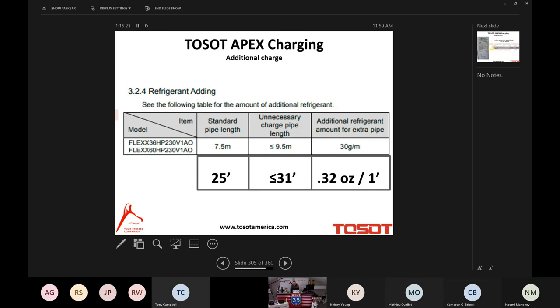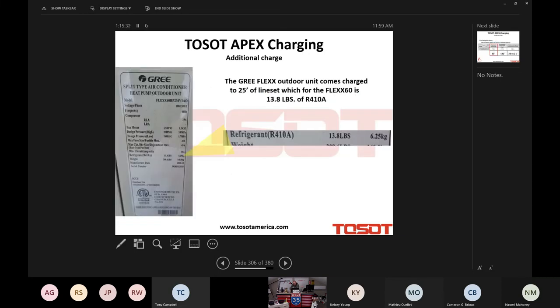Now, you can go beyond 31 feet. I told you that already. I told you you can go as far as 98 feet. And if you do, you are going to add 0.32 ounces of R410A for every additional foot. Again, not to exceed 98. So let's go back.